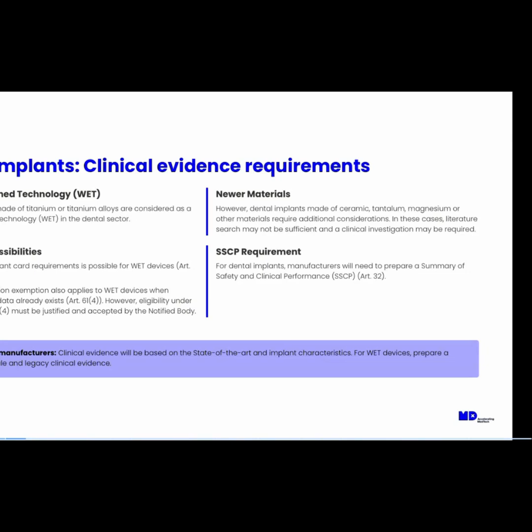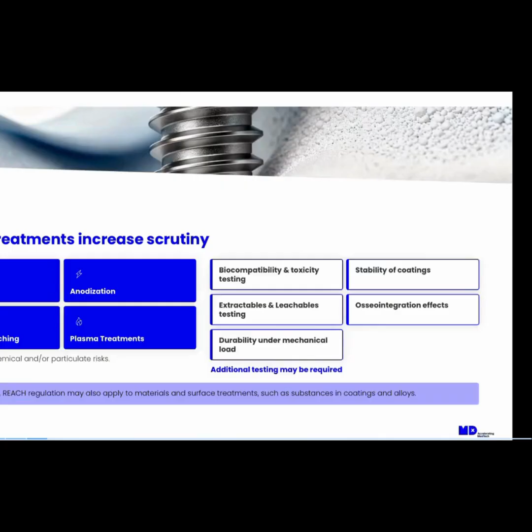As an implantable device, you still need to have the summary of safety and clinical performance. This is always a requirement for implantable devices and class 3 devices. However, you can be exempt from having the implant card requirements. So again, this is always going to be about whether it's considered to be the state of the art and the characteristics of the implants, but always prepare a robust justification and legacy clinical evidence to show and discuss with your notified body. Next slide.